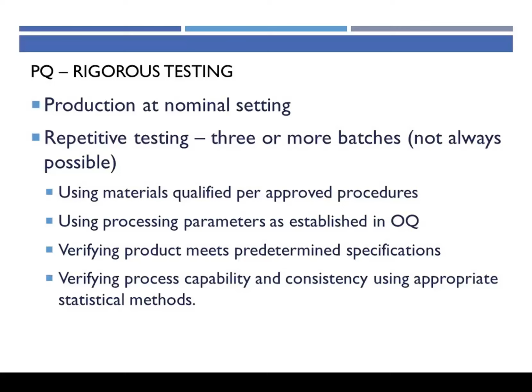Use materials that come in through your normal receiving inspection activities. Use the process parameters you've established during OQ. And you're going to want to take this product and show that it meets the predetermined specifications that you've defined in your protocol. And you want to show that your process is capable and consistent. That means you're going to have to use some appropriate statistical methods. The regulations require appropriate statistical methods.